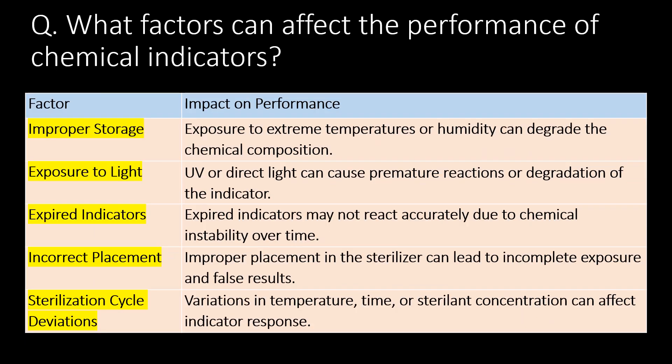What factors can affect the performance of chemical indicators? You can refer to the bullet table for the different factors that affect the performance of a chemical indicator. Key factors include improper storage, exposure to light, expired indicators, incorrect placement, and sterilization cycle deviations.